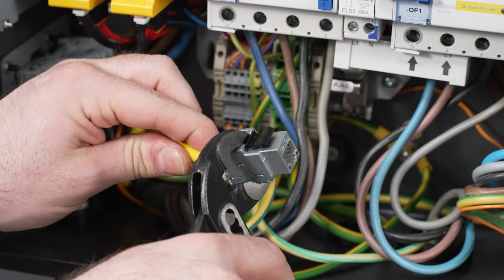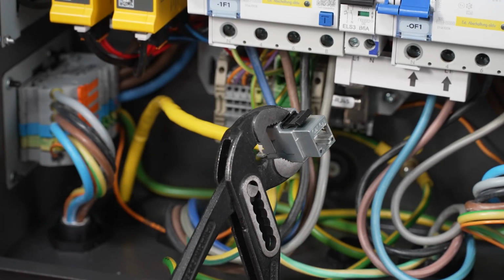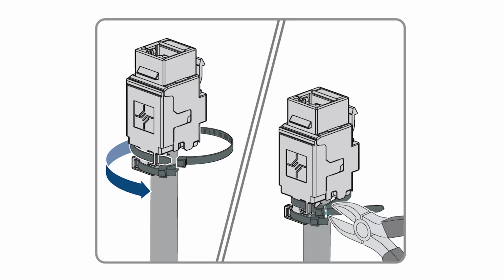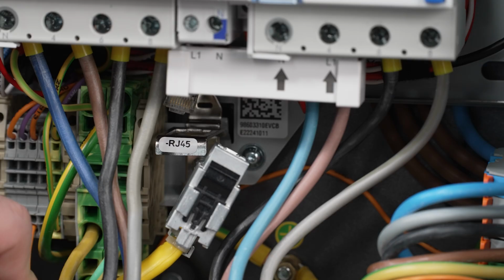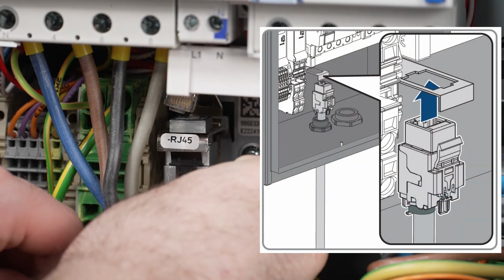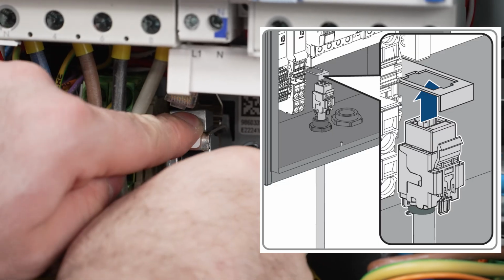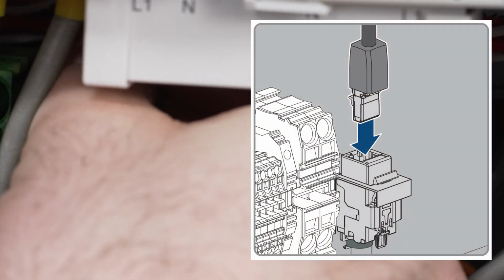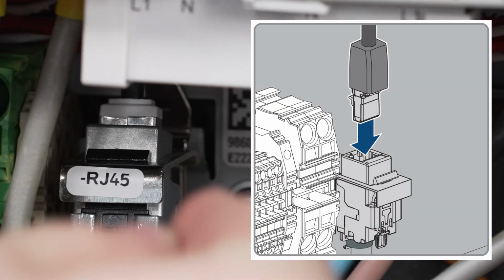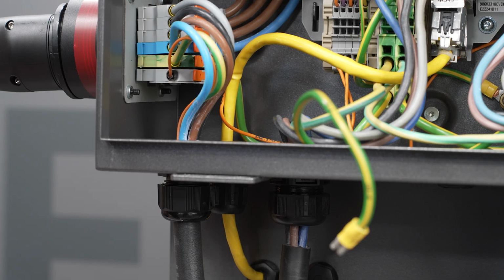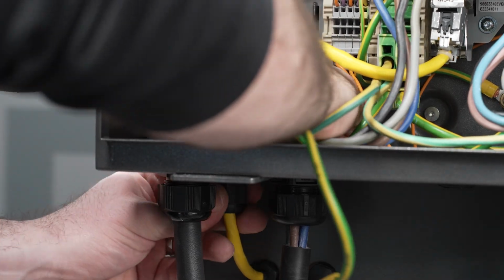Use pliers to press the two module parts together. Attach the second cable tie from the package and cut off the end. Snap the RJ45 module into the socket. Connect the network cable from the charge controller to the RJ45 module. Tighten the cable gland's union nut by hand.